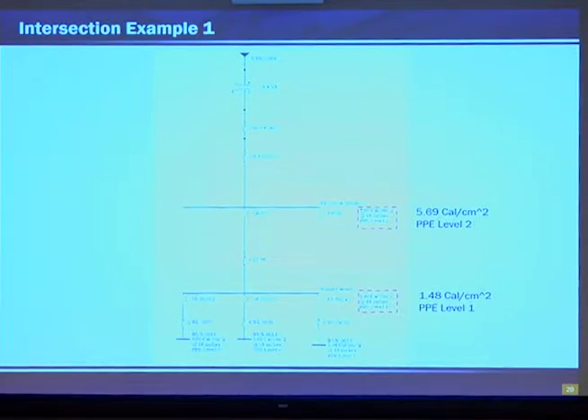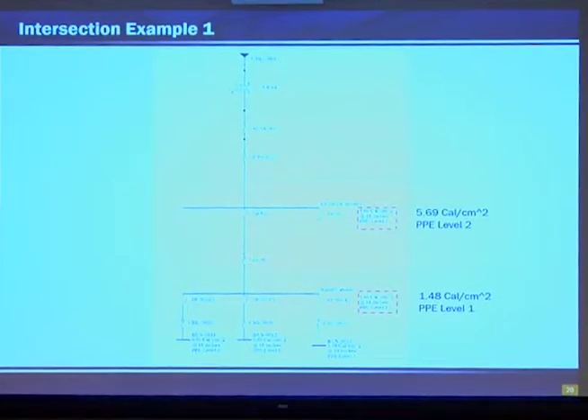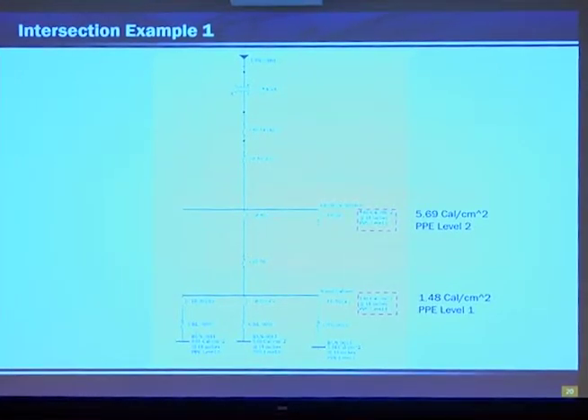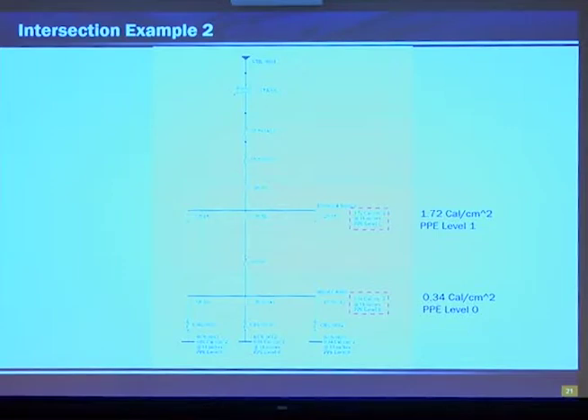So this intersection we calculated had an incident energy of 5.69 calories per centimeter squared and a PPE level of 2 at the electrical service. The signal cabinet had an incident energy of 1.48 calories per centimeter squared and a PPE level 1 at the signal cabinet. At this intersection, we calculated 1.72 calories per centimeter squared and a PPE level of 1 at the electrical service and a 0.34 calorie per centimeter squared incident energy at the signal cabinet with a PPE level of 0.